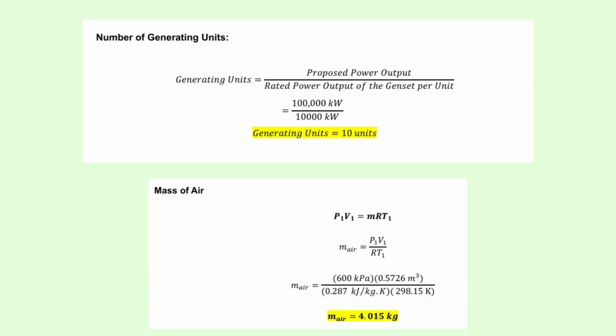Here we can see the number of generating units. To know the number of generating units, we use the formula: generating units equals proposed power output over rated power output of the genset per unit. So 100,000 kilowatts over 10,000 kilowatts gives us 10 units.